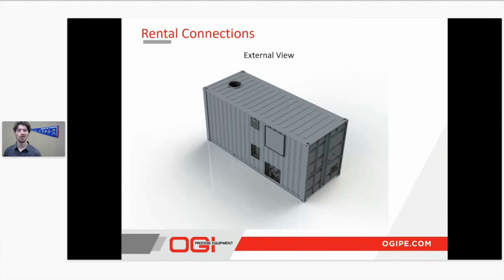So diving into our newest design for our rental heaters, I have an external view listed. With this, we're going to include our exhaust port. We have several vents all across the container, and a louver system, which we have programmed to open up as the QuikWater burner comes on. So when the EMS system is calling for heat on the QuikWater, that louver is going to actuate, allowing for the necessary combustion air on the blower for the QuikWater. So essentially, you don't need to have an external cover, since everything is covered and supported within our container here.